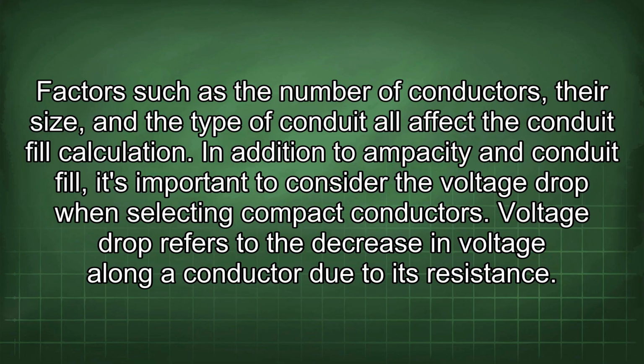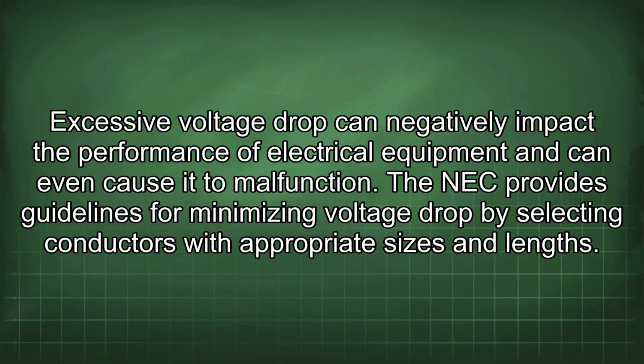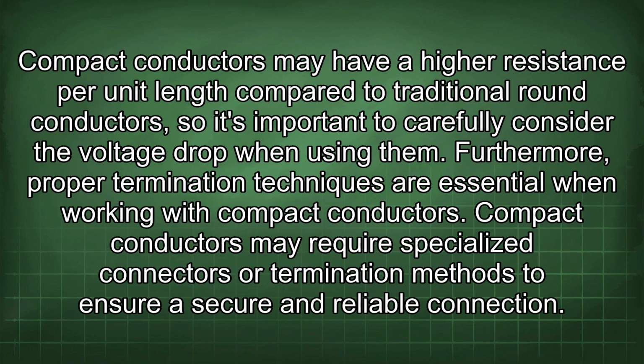In addition to ampacity and conduit fill, it's important to consider the voltage drop when selecting compact conductors. Voltage drop refers to the decrease in voltage along a conductor due to its resistance. Excessive voltage drop can negatively impact the performance of electrical equipment and can even cause it to malfunction. The NEC provides guidelines for minimizing voltage drop by selecting conductors with appropriate sizes and lengths. Compact conductors may have a higher resistance per unit length compared to traditional round conductors, so it's important to carefully consider the voltage drop when using them.